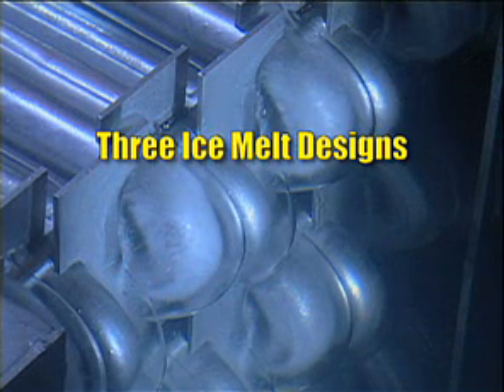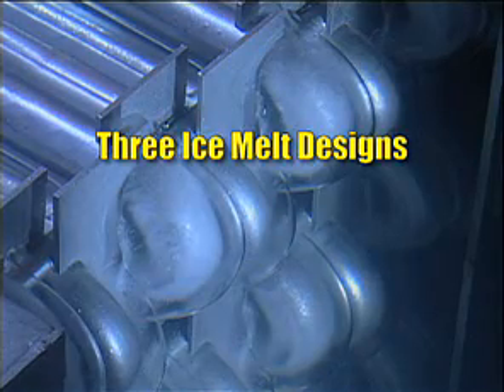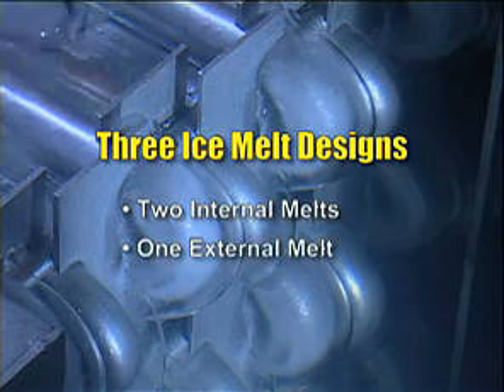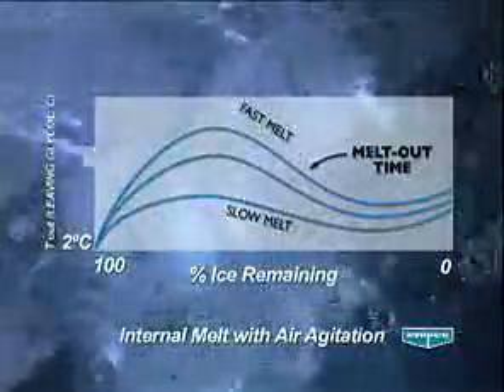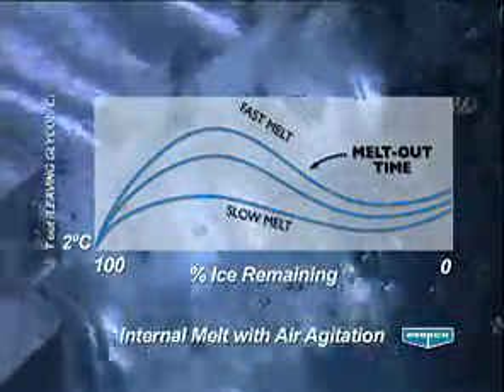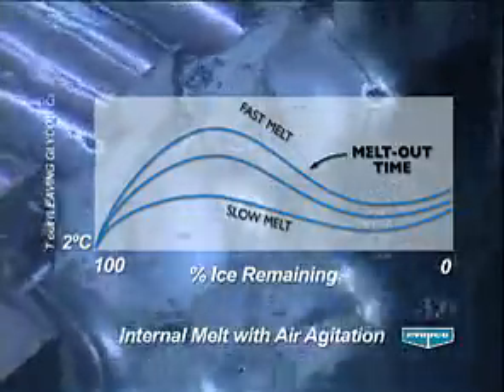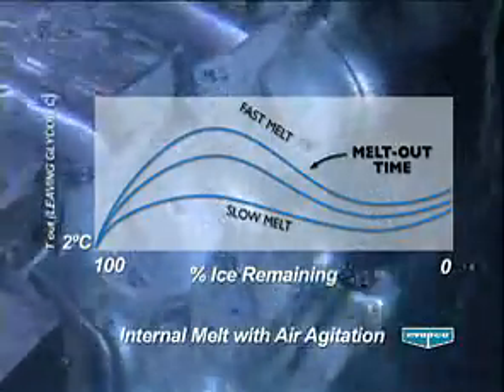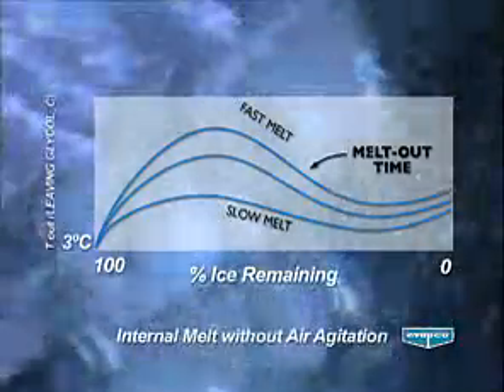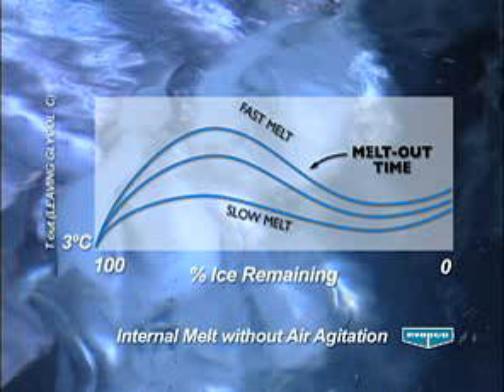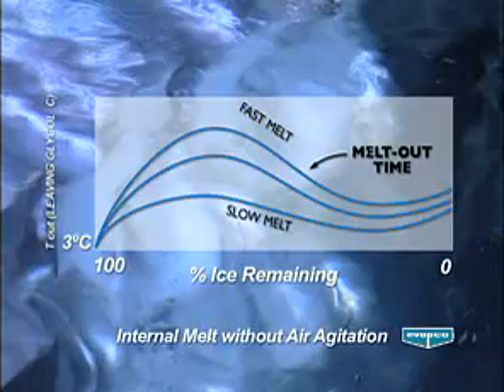Evapco offers 3 ice melt system designs: 2 internal melts and 1 external melt. The internal melts are generally for single building applications or small systems. They are internal melt with air agitation, which can provide 2 degrees centigrade supply glycol, and internal melt without air agitation, which can provide 3 degrees centigrade supply glycol.